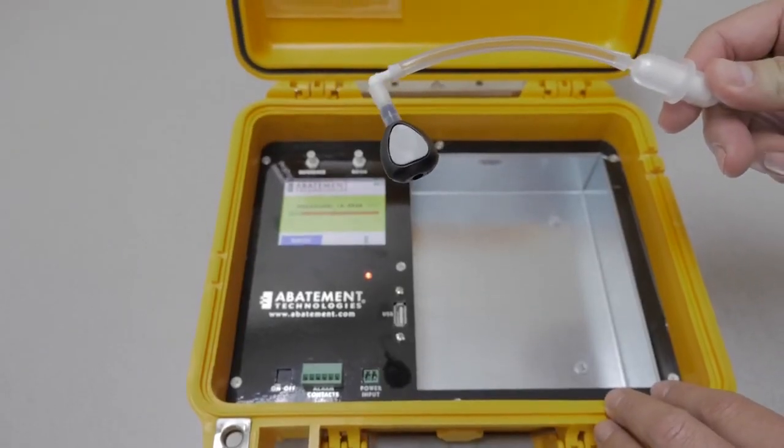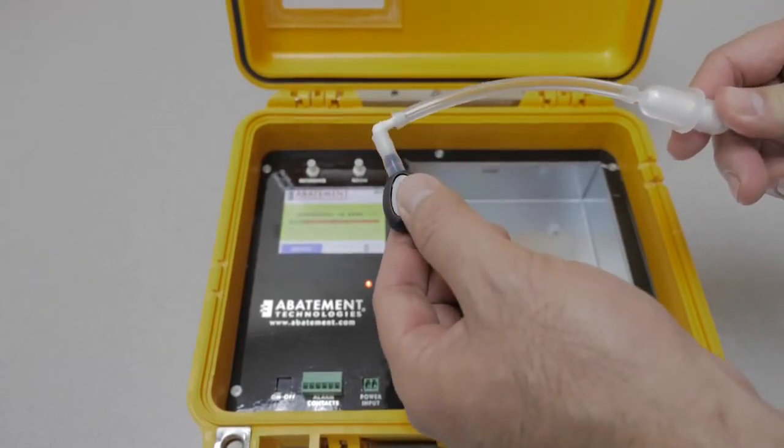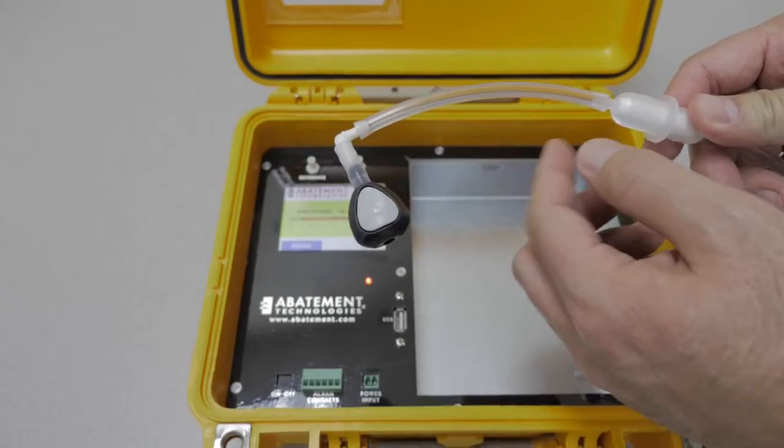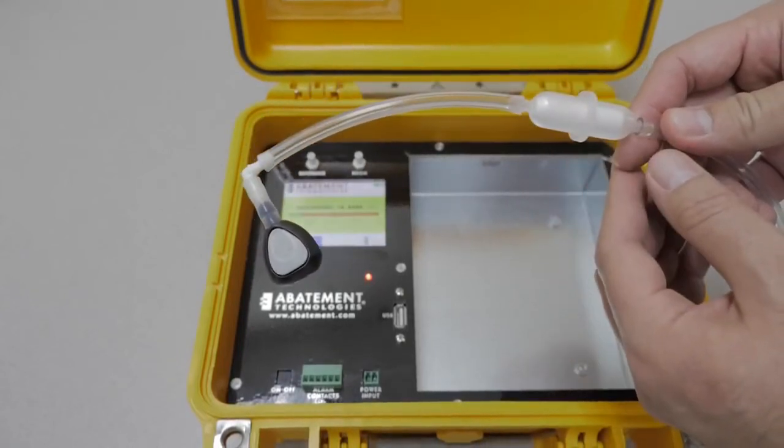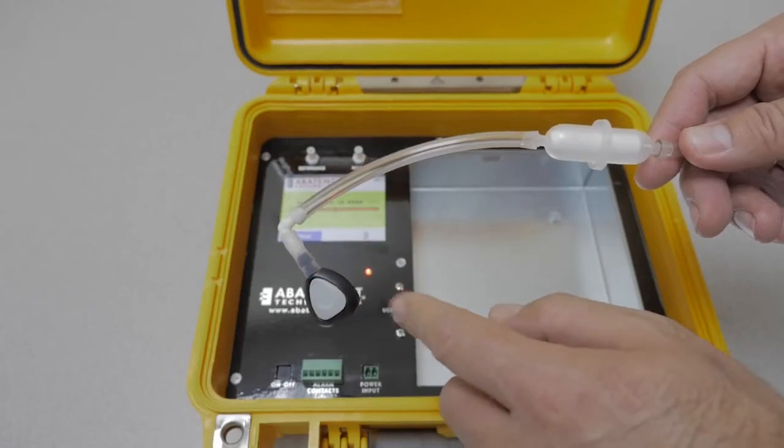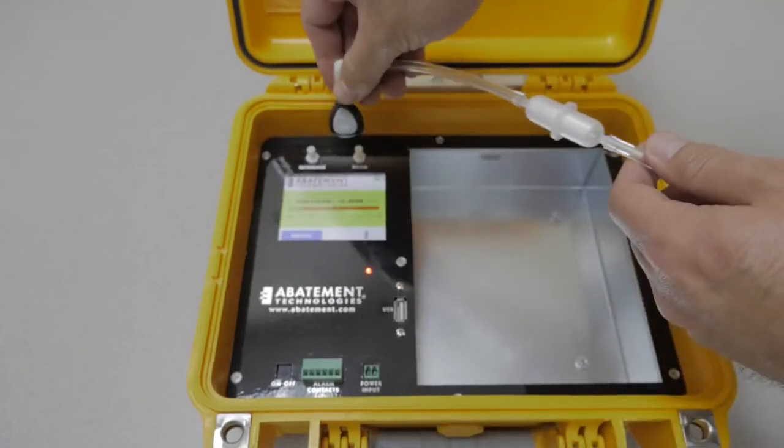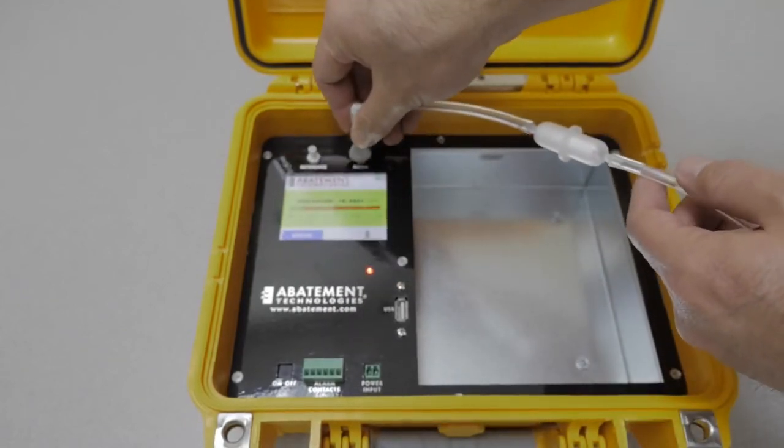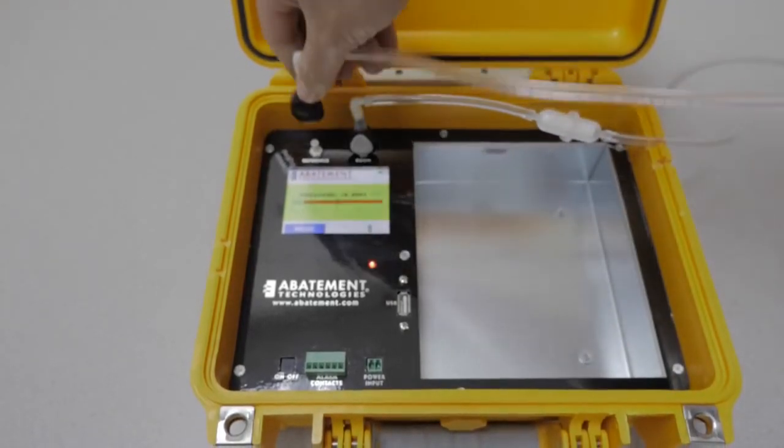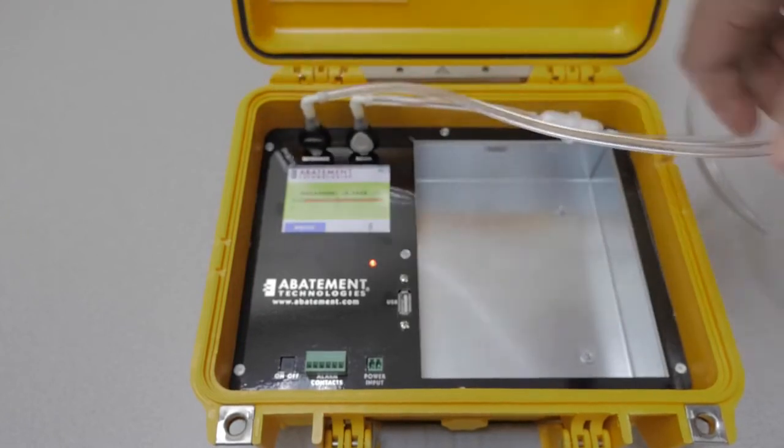To set up the monitor for negative or positive pressure monitoring, the quick connect connects directly to the monitor. Attach your tubing to the quick connect. Make sure that the arrow on the filter is pointed towards the monitor. Then just snap the tubing onto one of the ports. Repeat the same procedure for the other tubing.